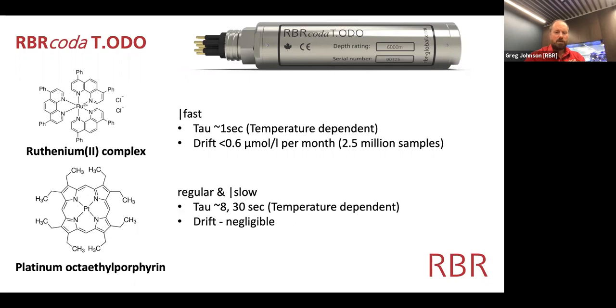That fast foil has a 1 second time constant and reasonably high drift, 0.6 micromole per liter per month, assuming that you illuminate about 2.5 million samples. And that drift really is a function of how much light it sees. So if you keep it dark, it doesn't drift at all. If it's in your cupboard or in your drawer waiting for a deployment, you don't have to worry about drift then. But I wouldn't leave it exposed to sunlight, for instance, because it will drift under those circumstances.